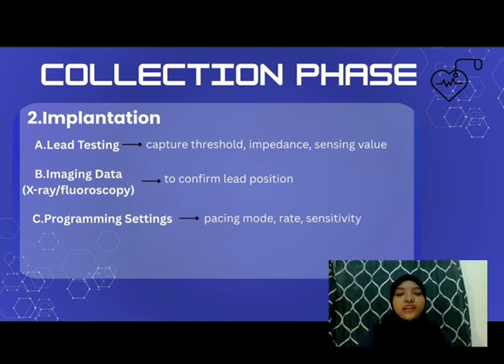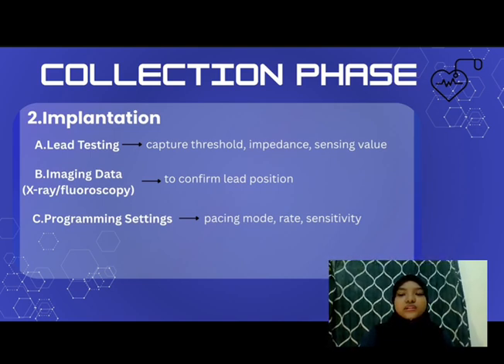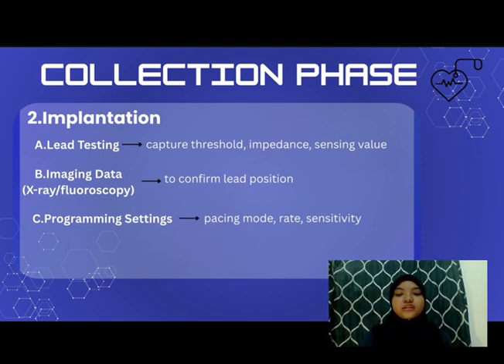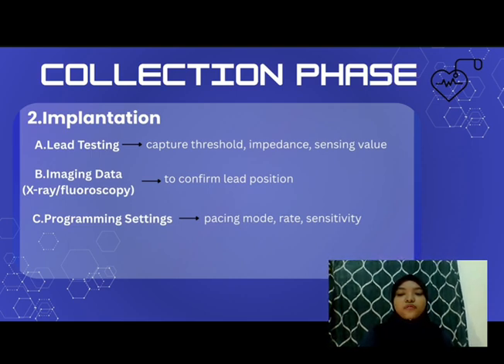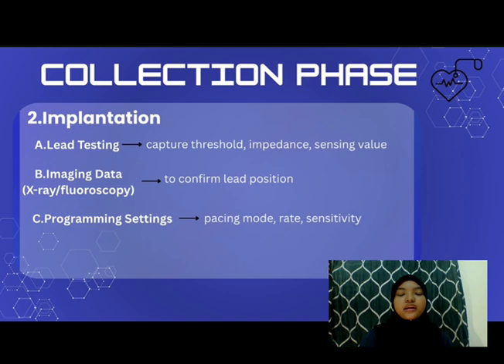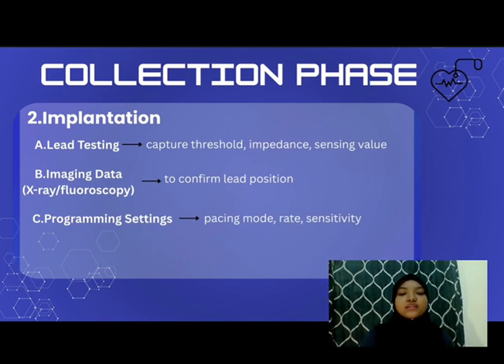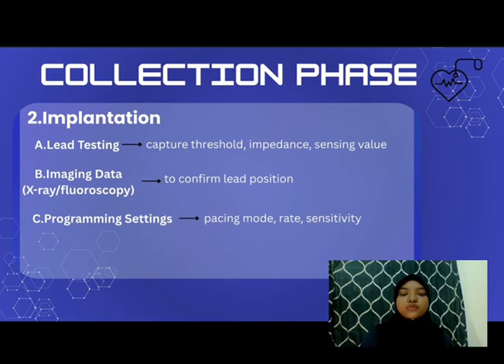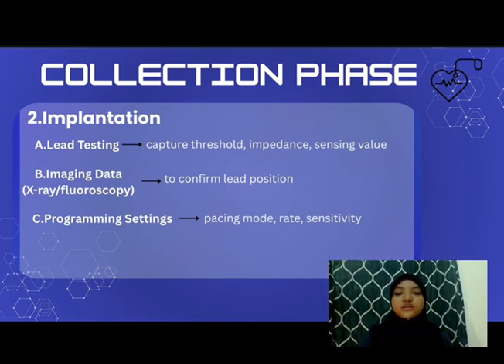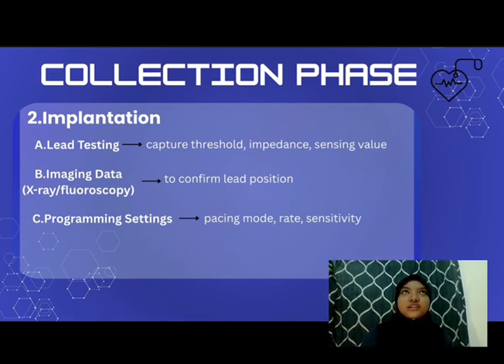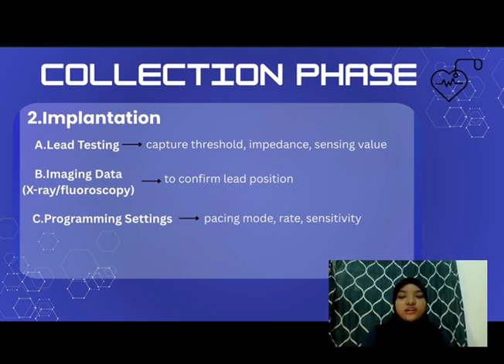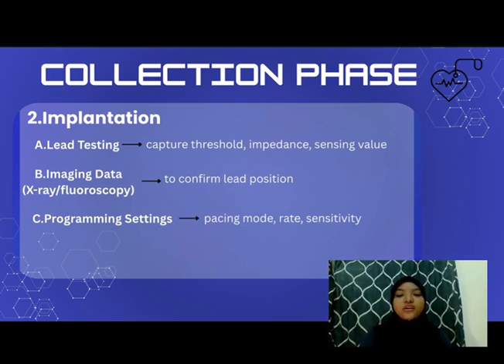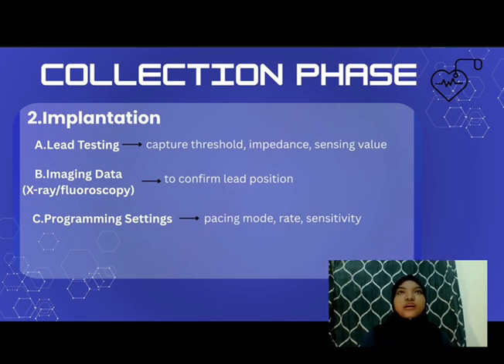Second is impedance, which is the resistance in the pacing circuit, which helps confirm that the lead is intact and not damaged. After that are sensing values, which is the ability of the pacemaker to detect the heart's natural electrical signals. These tests ensure that the leads are working efficiently and are in good contact with the heart tissue.